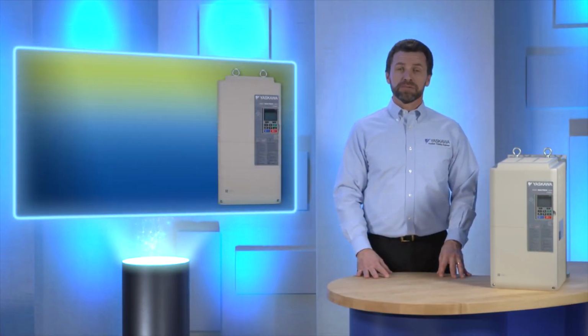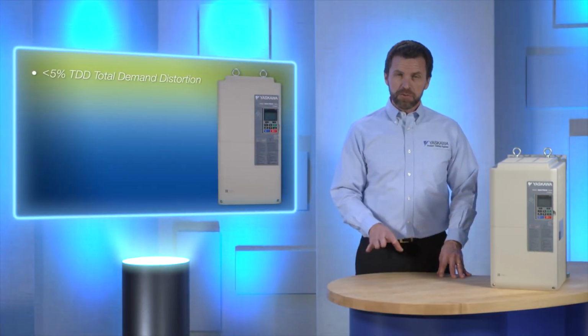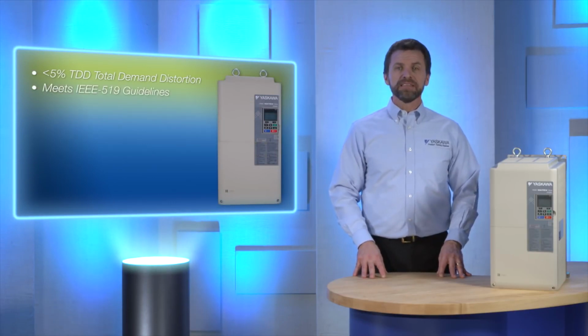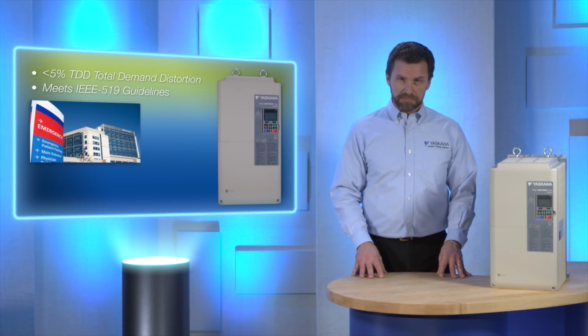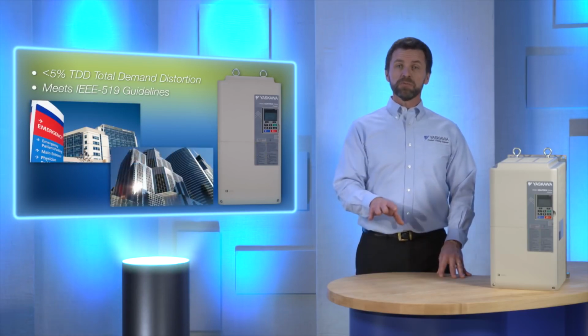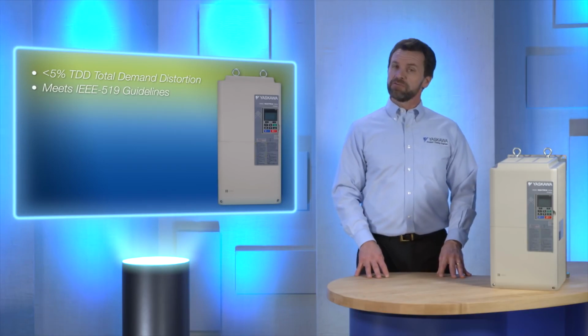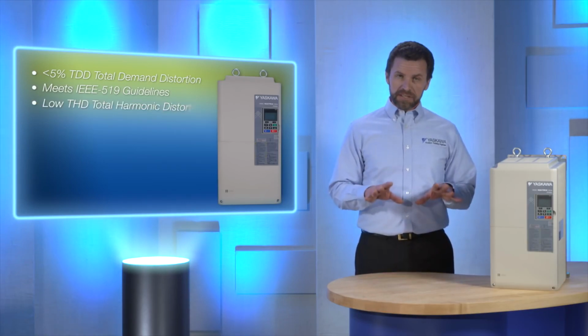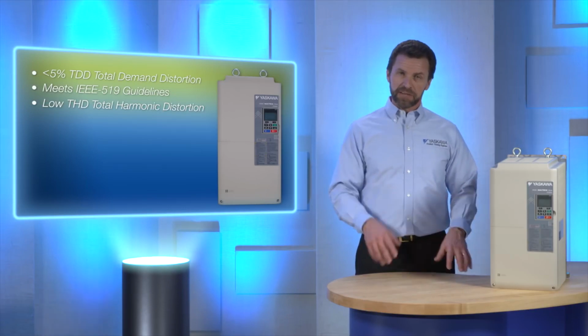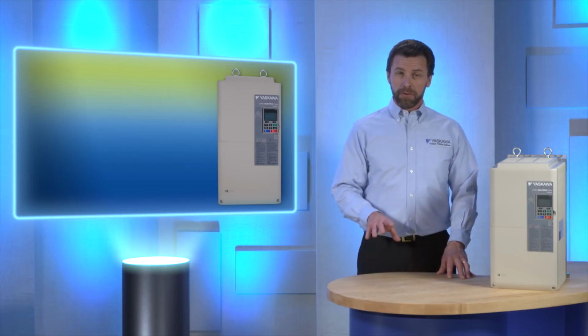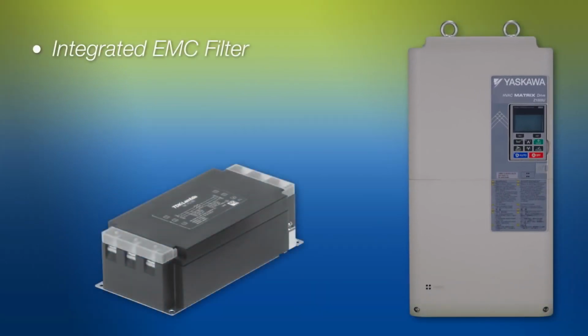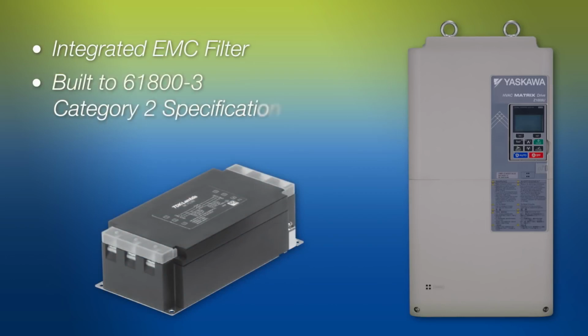Because current harmonic characteristics are less than 5% TDD, the Z1000U meets IEEE 519 guidelines, making it ideal for hospitals and commercial buildings. In fact, the Z1000U exceeds the expectations of IEEE 519 by maintaining low THD through the typical operating ranges of HVAC applications. Remember, the Z1000U has an integrated EMC filter to prevent radio interference. The filter is built to the 61800-3 Category 2 specification as laid out by the IEC. It meets all pertinent FCC standards as well.